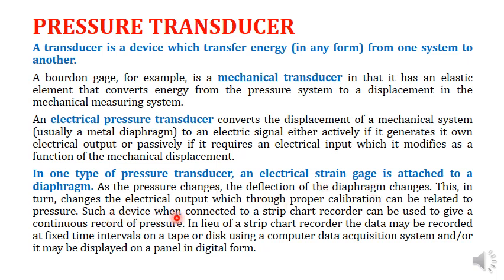An electrical strain gauge is attached to a diaphragm; as pressure changes, diaphragm deflection changes the electrical output, which through proper calibration can be related to pressure. Such a device connected to a strip chart recorder gives a continuous pressure record. Alternatively, data can be recorded at fixed time intervals using a computer data acquisition system, or displayed on a panel in digital form — enabling digital, graphical, or tabular reporting of pressure values.